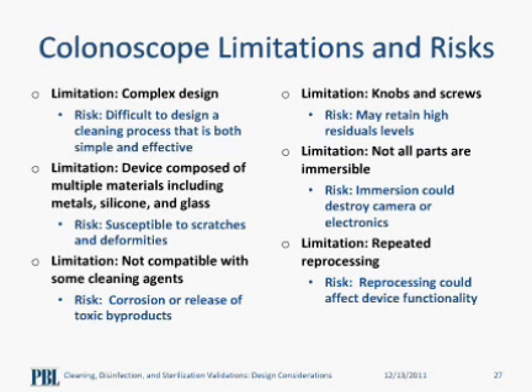This device is composed of metals, silicone, and glass, which are more susceptible to scratches and deformities. Some of these materials are not compatible with some cleaning agents, as their use can result in corrosion or release of toxic byproducts. The knobs and screws are potentially trouble spots for retaining high levels of residuals. Not all parts can be immersed in fluid. We have to be extra careful to protect the delicate parts to prevent breakage of the lens, camera, or destruction of any electronic components. Repeated reprocessing can also affect the functionality of the device.